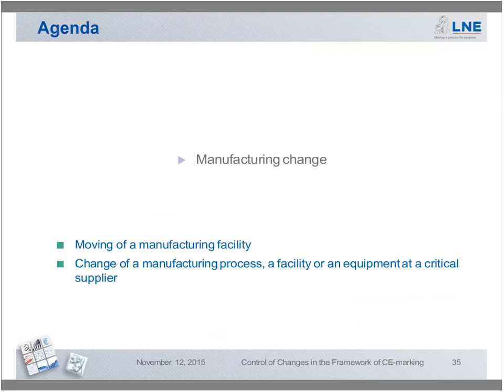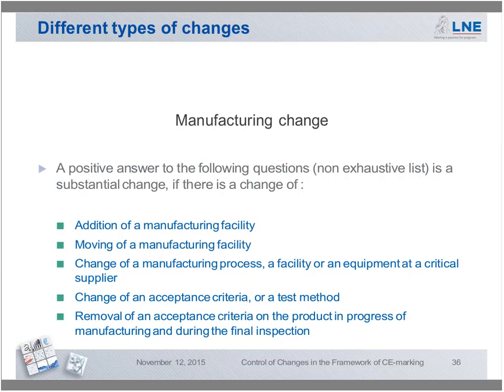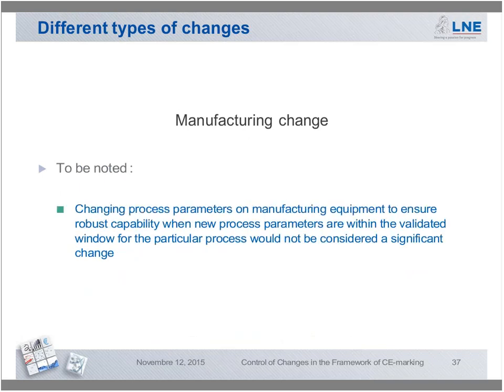For manufacturing change, it can be addition of a manufacturing facility, moving of a manufacturing facility, change of a manufacturing process, a facility or an equipment at a critical supplier, change of an acceptance criteria or a test method, removal of an acceptance criteria for the product in progress of manufacturing and during the final inspection. So to be noted, changing process parameters on manufacturing equipment to ensure robust capability when new process parameters are within the validated window of a particular process would not be considered as a significant change.